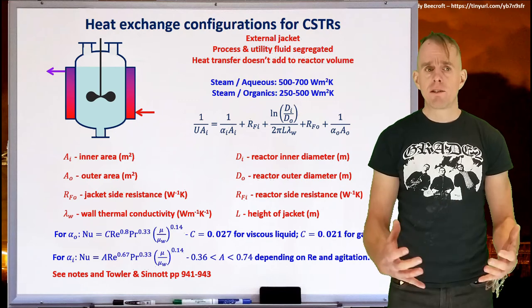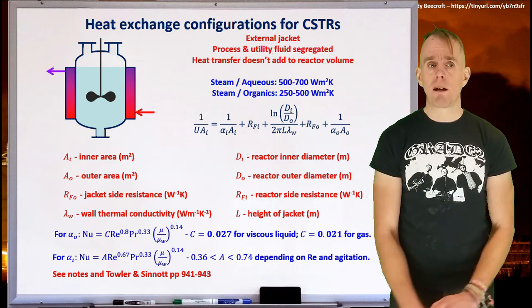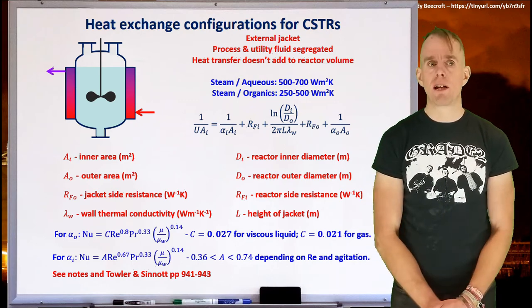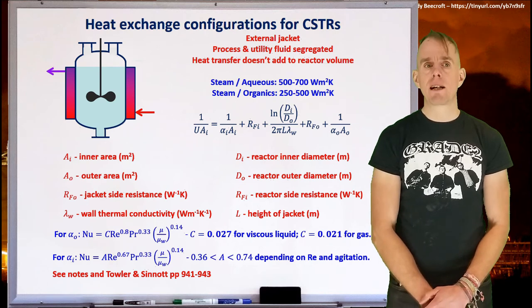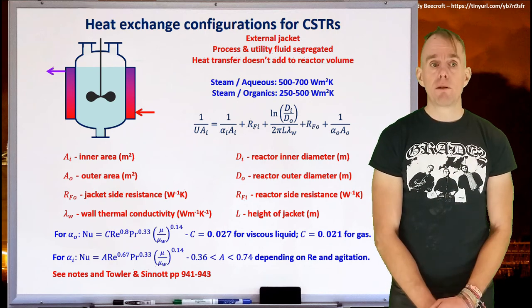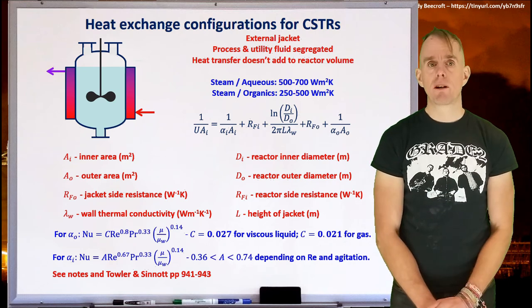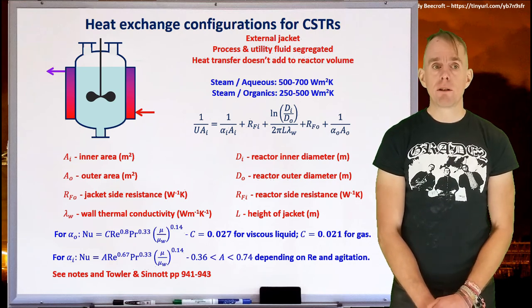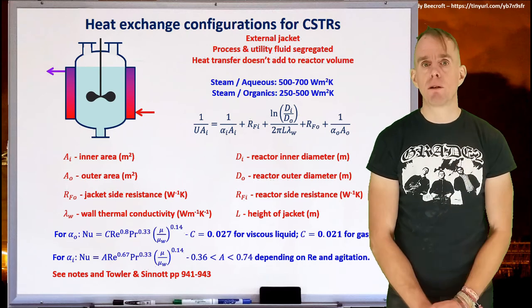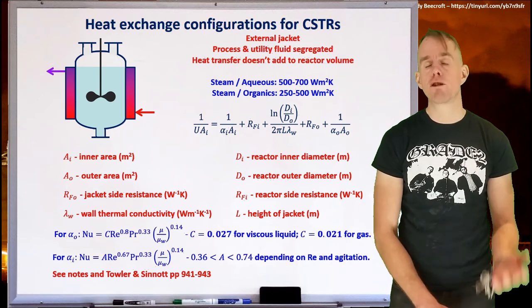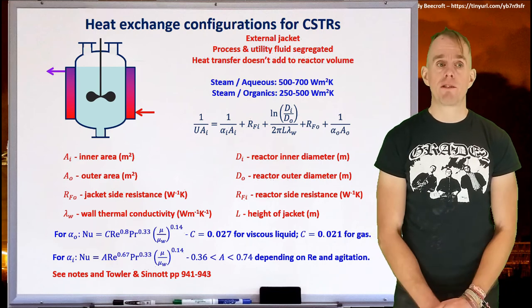If you've got an agitated system, again, different correlations will apply. And I've put a second Nusselt number correlation here on the board for you that allows you to calculate the inner film resistance due to a stirred tank. There's a lot more of these correlations in the literature. And if you look at Towler and Sinnott's excellent book on chemical engineering design, pages 941 to 943, you'll see far more listed.